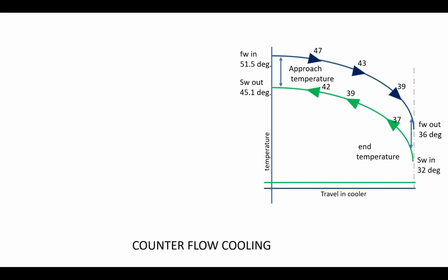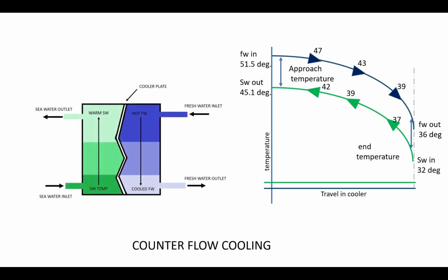Let's see the values at our central cooler. Fresh water enters the cooler at 51.5 degrees and will leave the system at 36 degrees Celsius, while seawater enters the cooler at a temperature of 32 degrees and will leave at a temperature of 45.1 degrees Celsius. The fresh water outlet temperature is less than the seawater outlet temperature with counterflow.